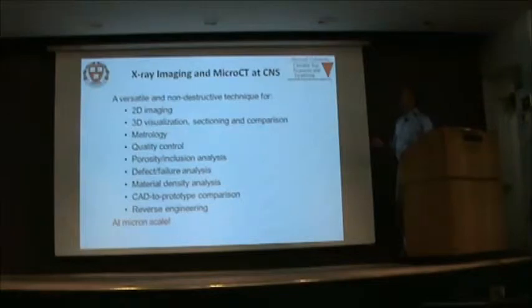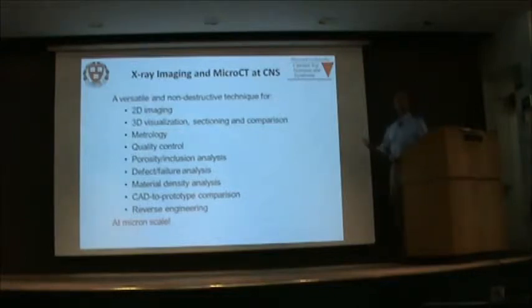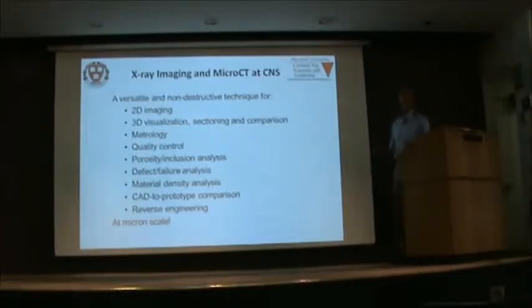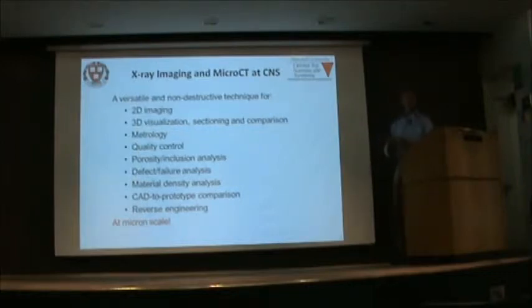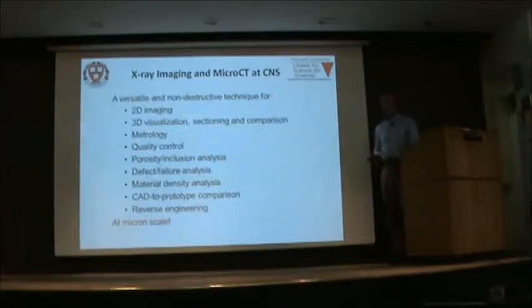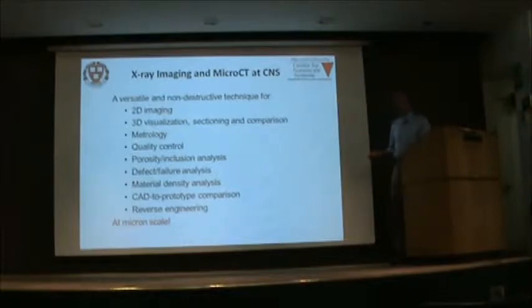For those of you who don't know about MicroCT, it's a very versatile and non-destructive technique. It can be used for 2D imaging, 3D visualization, and sectioning or comparison of actual versus design parts. You can do metrology measurements on your samples, quality control to check if a part conforms to the original design, porosity or inclusion analysis, defect or failure detection, material density checks using density standards, and CAD-to-prototype comparisons.